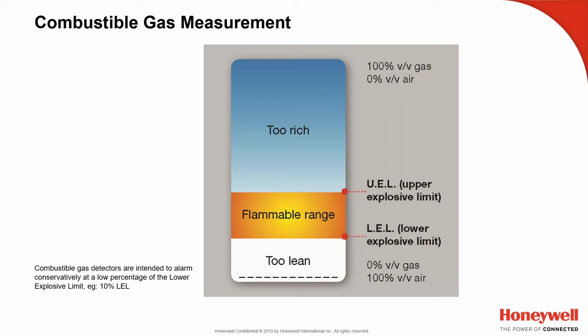What the gas monitor will do is detect the range before you get into the flammable range, and even give you an early warning alarm at 10% of that LEL. So you have early warning to not even mess around. If it hits 10%, you need to get out and remedy the situation, whether it's through ventilation or time. But best practice for hot work, if you're doing welding, is to set that lower alarm to 5%, because it is more critical in that particular application.